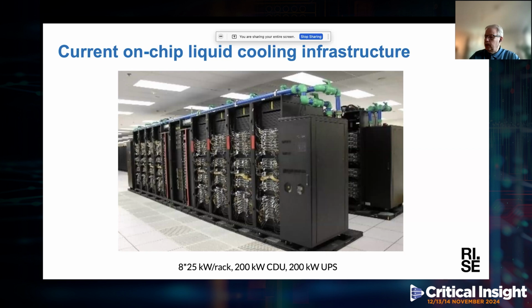Okay, so what is going to happen with the infrastructure then? If we just take a supercomputer of today, maybe it looks like this. You have 8 racks here with 25 kilowatt per rack compute, and you have a 200 kilowatt CDU, and a 200 kilowatt UPS, liquid cooled, so it will be a row of equipment. You have probably seen that in a number of places. This is a regular supercomputer, I would say, an HPC machine as we call them in Europe.